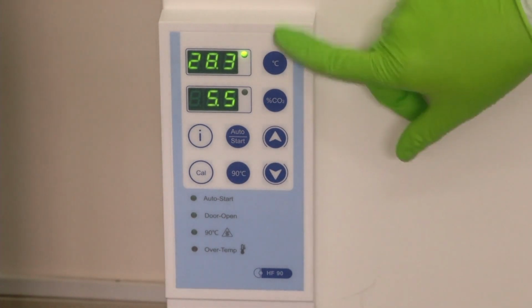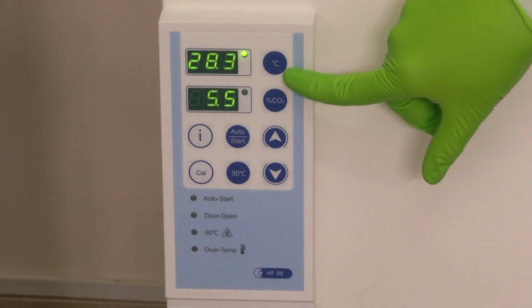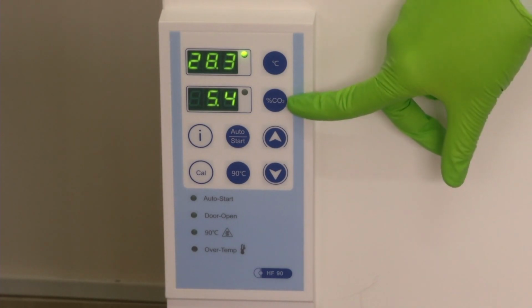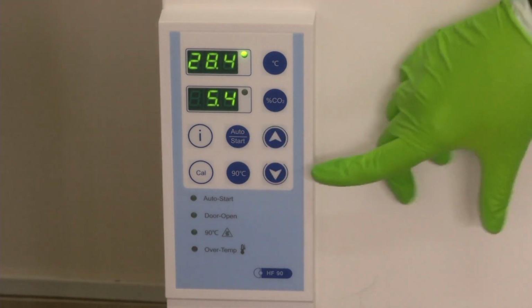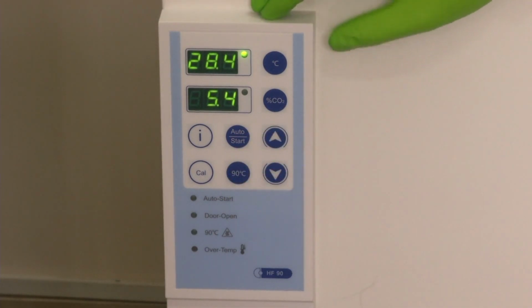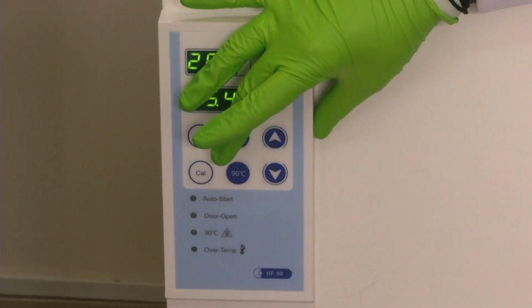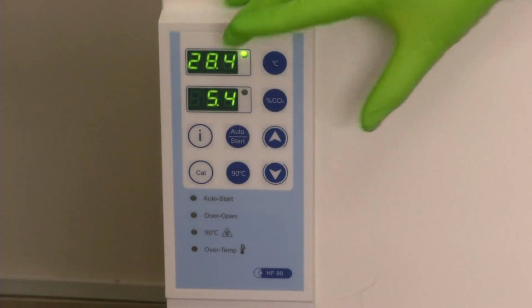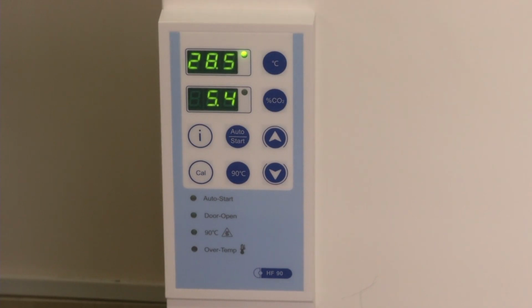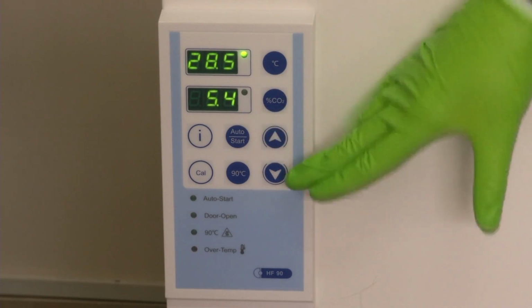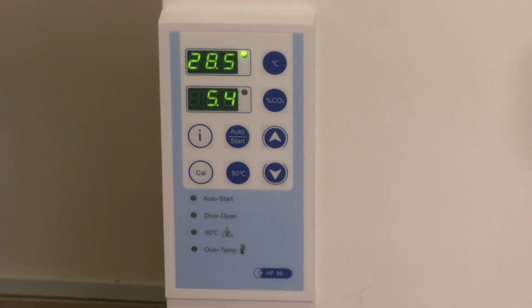See here, you see buttons. These are all touch panel buttons. This is degree Celsius: what is the temperature that you have set? This is percentage CO2: what is the percentage CO2 that you have set? And auto start: how do you want to set it to auto? Then the 90 degrees Celsius. What is this? This is for routine sterilization. As I said, contamination is a very important thing, so we have to routinely sterilize our incubator inside. If you click 90 degrees Celsius, it will create a 90 degrees Celsius environment inside the incubator and kill any bacteria that might be present. So, this is used for cleaning the incubator. Right now, we will not use it. Cal is for calibrating everything properly, so that if you set 5% CO2, actually 5% CO2 should be maintained inside. That calibration it will set.